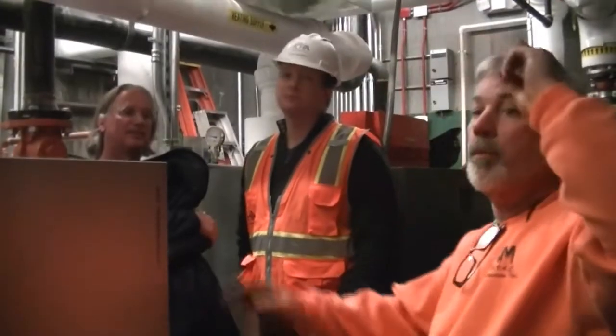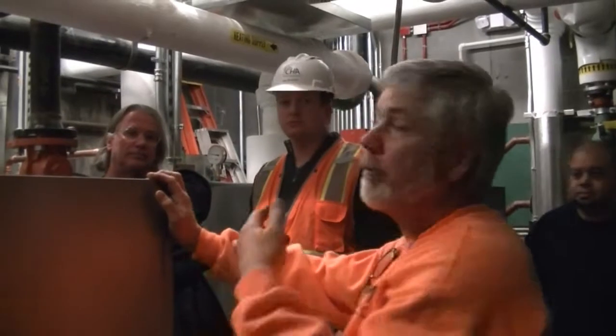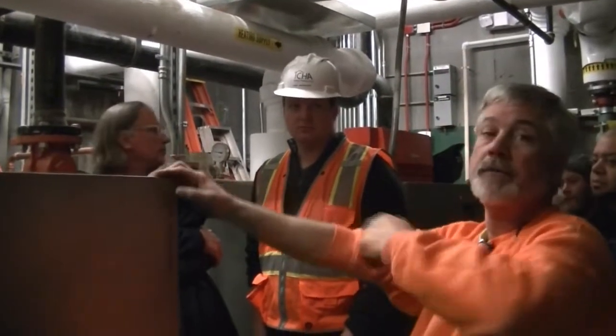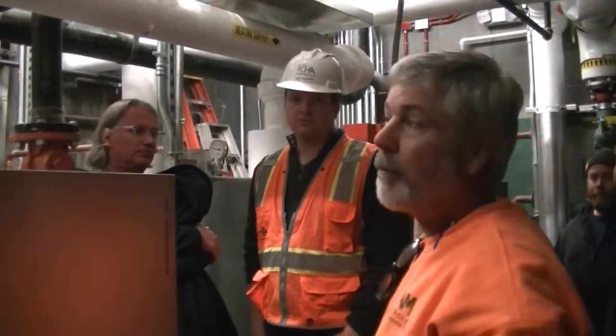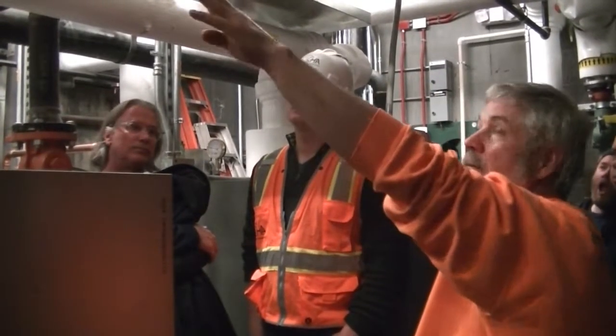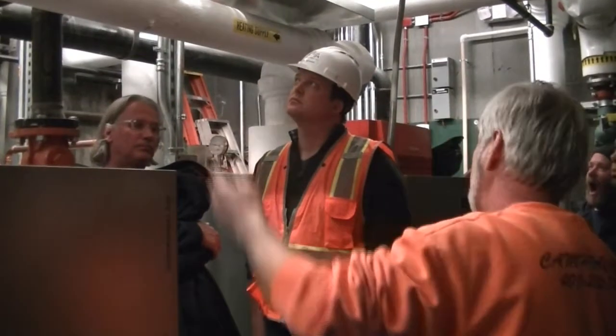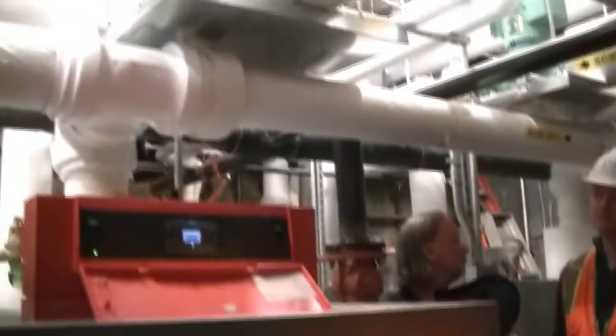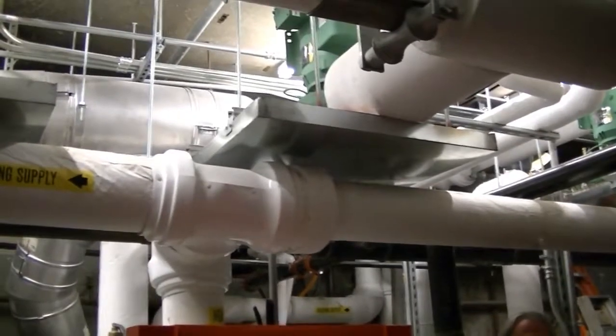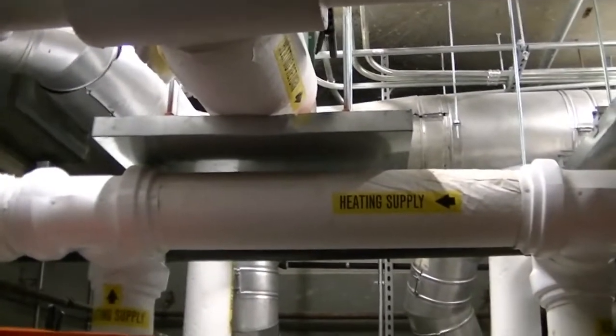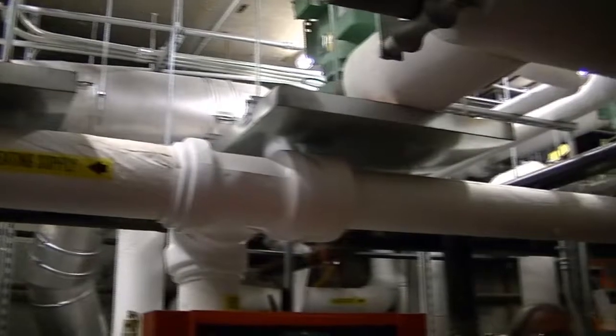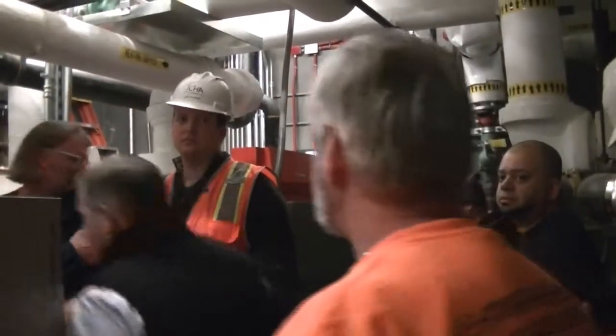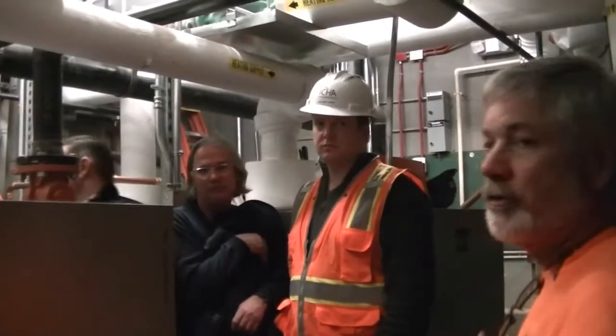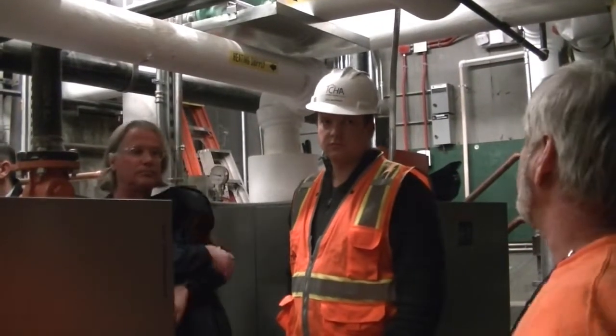That pump is to pull water out of the header, force it through the boiler, and back out into the header in order to supply the three-way valve with hot water. There are grease fittings on the pumps, okay? Every 6 months, check the grease. A lot of maintenance schedules will tell you, check it every month. Well, you can start out by doing that. But if you don't see excessive wear, or if you don't see the pump start chewing through grease, you can delay those maintenance checks out further.